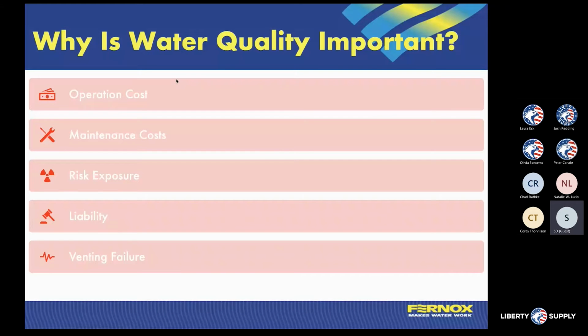Obviously, maintenance costs: we're going to talk about how this affects heat exchangers and components such as valves and strainers and different things in your system. You're going to have to replace those more frequently, and you're going to have to do maintenance to keep them from leaking and from failing prematurely. There's a risk exposure to the owner of whatever facility we're talking about, whether it's a residence or a commercial building. A lot of the manufacturers of different pieces of equipment and components are no longer going to warranty things that fail due to water quality issues. They don't feel like that's an installation issue. They feel like that's a failure from exposure to the water quality in that particular system.